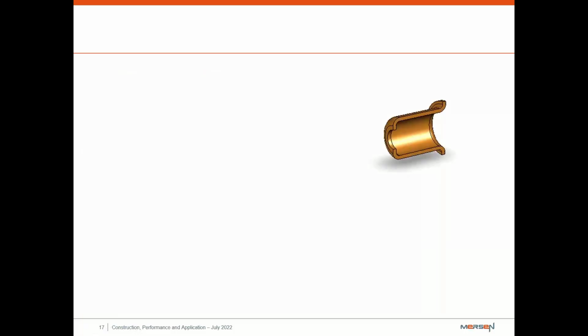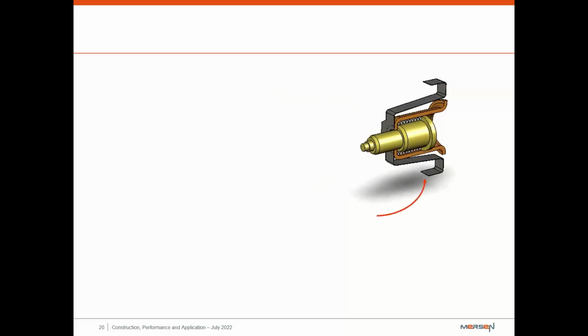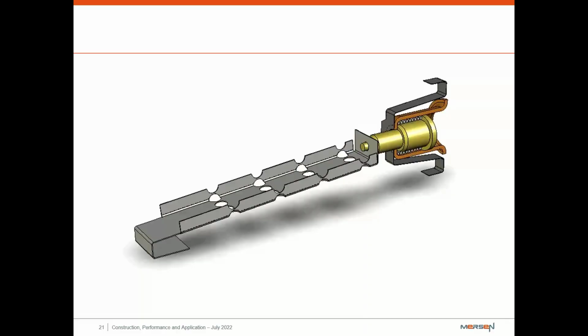Getting into our RK1 styles, you're going to have our spring plunger assembly, and inside you're going to have a spring. Now the key is that this is a compressed spring, and that'll make sense in a second. Then we're going to have our plunger, our heater connected to the outside, and then our short circuit element. The same thing applies with this, where we have our piece of solder here. So in the case of an overload where you're not at 10 times rated, but you're outside the band of normal operation, this piece of solder starts to heat up. The solder will turn into a liquid. Once it does, this compressed spring will pull the plunger forward, opening the circuit.